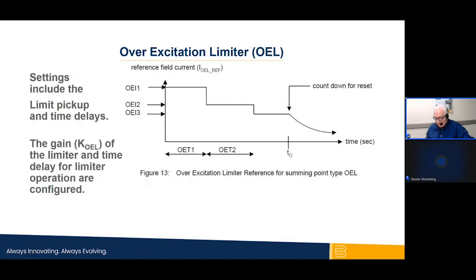The operation of the machine while connected to the bulk electrical systems will call for short time overloads, which will require levels of field current that exceed the continuous capacity limit. There are established standard short time thermal capabilities that machine builders observe in the design of the rotor, its windings, its cooling system, and the insulation systems. The basis of the short time capability is the relationship between the heating during the overload period and the machine's ability to absorb the heat without failure. The limiter picks up when the field current is sensed to be above the value configured as the limit. The action of the limiter is based on the amount of time and the difference between the limit value and the magnitude of the field current.